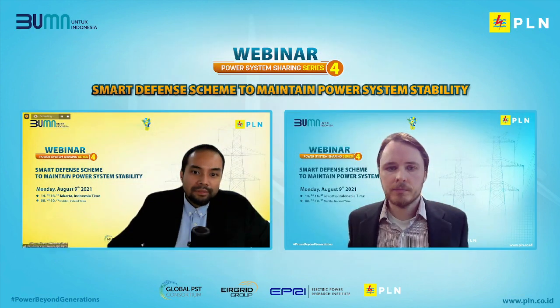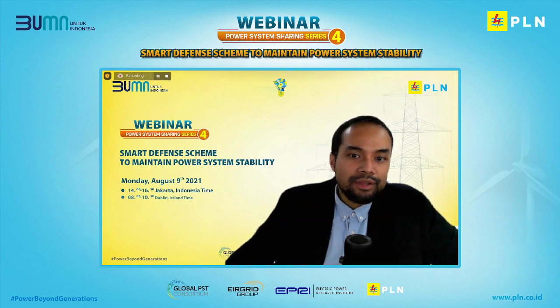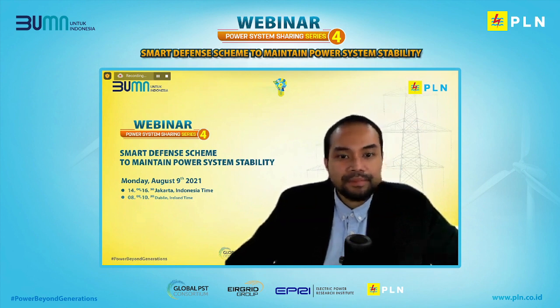We need to always update the study or contingency. We need also to test the scheme on a regular basis to make sure that the defense scheme is working well and has no interaction with other defense schemes. And finally, we need to create a control center operator guideline to mitigate every probable risk. When something happens with the defense scheme, the operator must know what to do and so on.